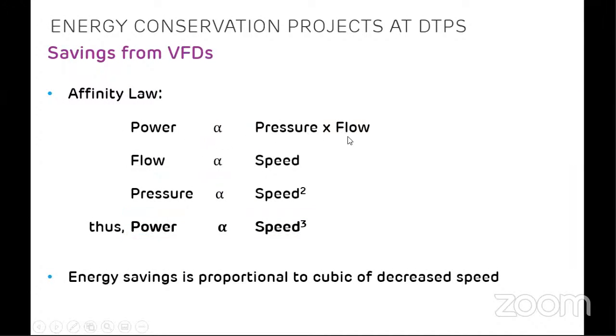Power is proportional to pressure and flow, as we know from the affinity law. Flow is proportional to speed and pressure is proportional to the square of speed. Thus, power is proportional to the cube of speed. So a very small variation in speed leads to very large savings in power. Suppose, for example, you have an auxiliary running at 3000 RPM, but the required flow demands that it should run only at 2900 RPM. This small reduction of 100 RPM gives very large power savings as power is proportional to the cube of the speed.